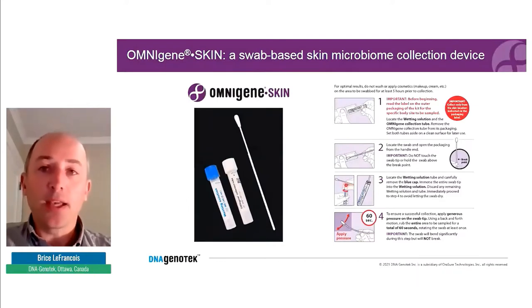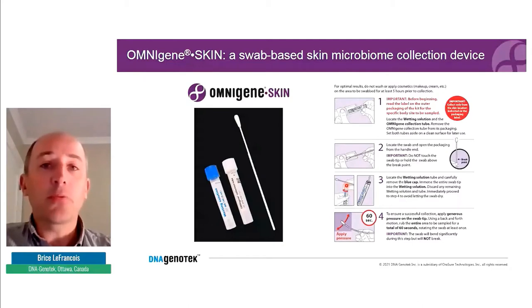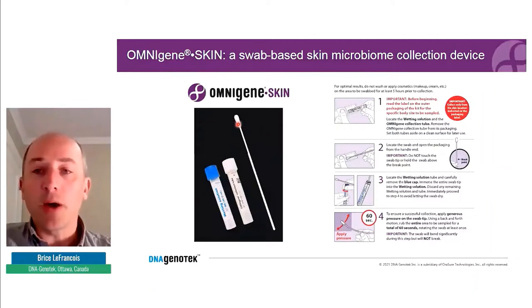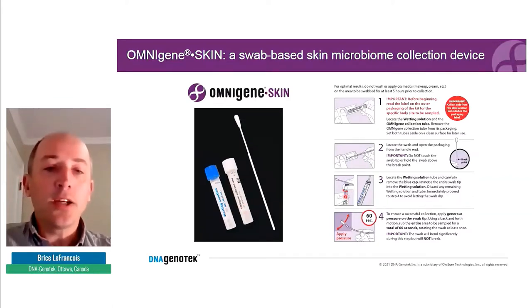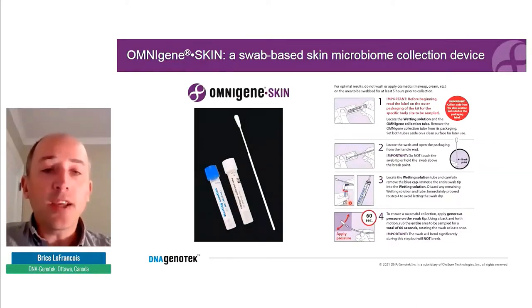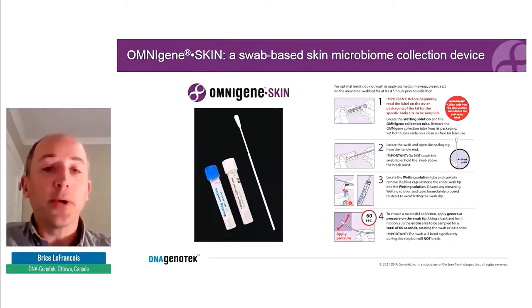So we decided to leverage our knowledge at DNA Genotek, and we developed OmniGene Skin, which is a swab-based collection device. It's very simple — it consists of a flocked swab with a breaking point, an OmniGene collection tube containing one milliliter of a stabilization solution, as well as a wetting agent. The IFUs are provided with each kit, and we spent quite a bit of time working on them, because to get good quality skin samples, you really need the end user to collect as well as possible.